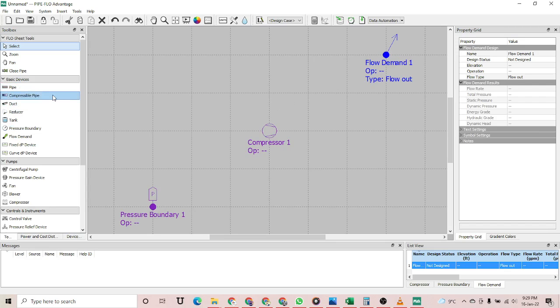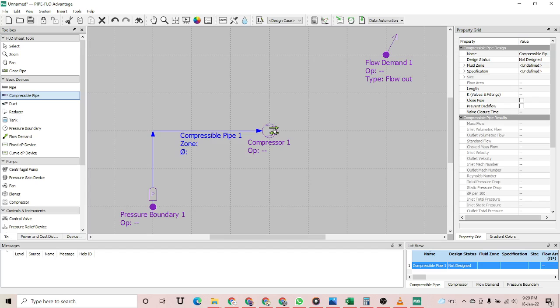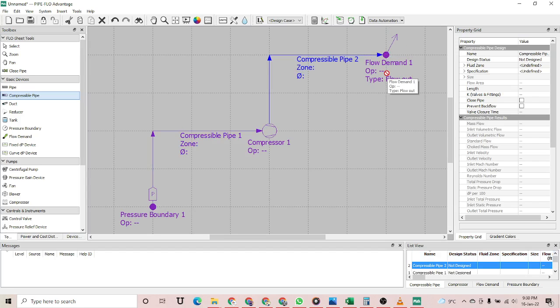Whenever there is a compressible fluid in your circuit, you should use a compressible pipe. Our circuit contains a compressor, and the compressor would significantly change the pressure of our fluid, so we have to use a compressible pipe. A simple pipe would be used for hydraulic calculations where the fluid pressure would not change significantly. A compressible pipe is used because the fluid would be compressible.